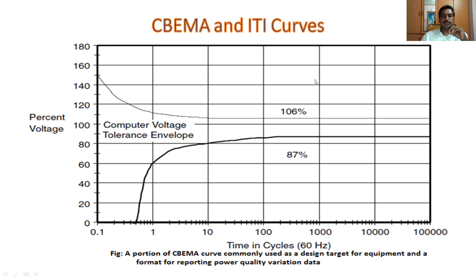But after some modifications, the Information Technology Industry Council designed a new curve. Next we go through this ITIC curve, which is the modified curve. From this modified curve, you can understand that below the dotted line is due to the low energy requirement of the computers. Above this portion, due to sudden short circuits or fault conditions, this much high voltage will be obtained.